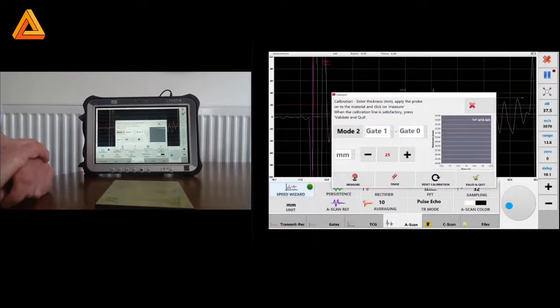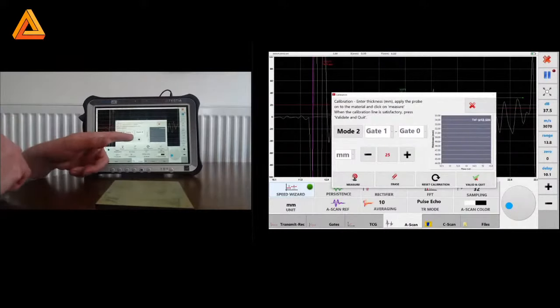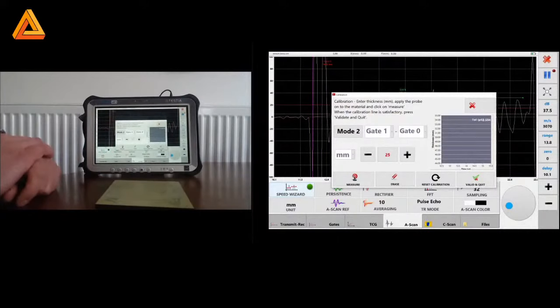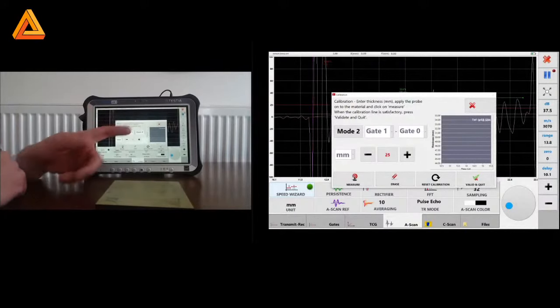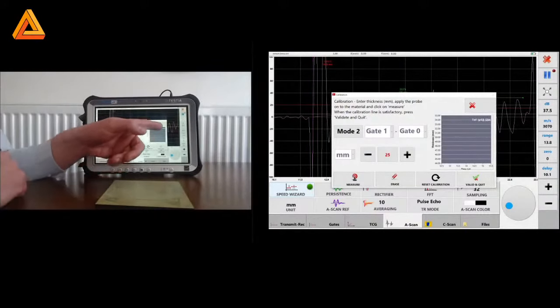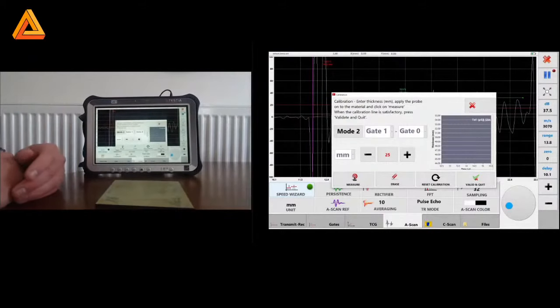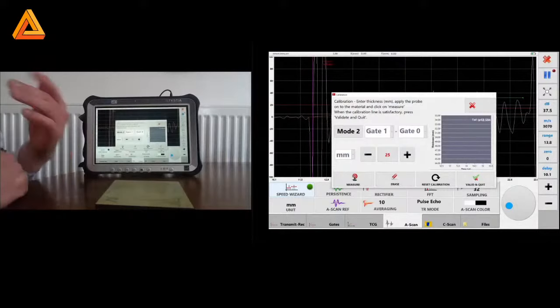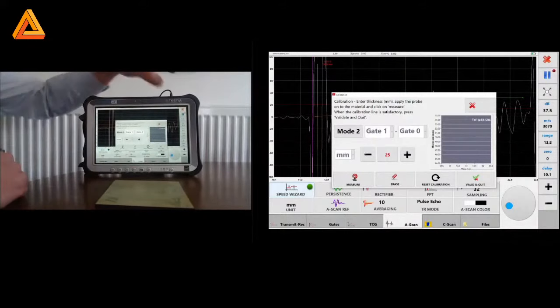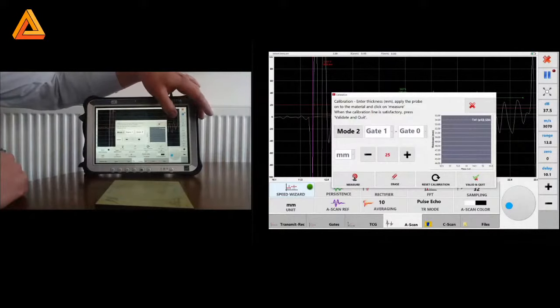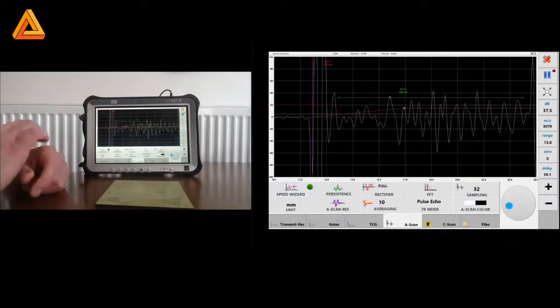Do an auto calibration for velocity, and we simply do this by entering in the thickness of the material where the red 25 is, and we can do this for multiple steps, and the system will then produce a straight line graph. It's a nice visual representation, so if one of your calibration points is off, we can see it visually during calibration, and we can erase those points and start again. Once we're happy with it, we press validate and quit, and it will automatically calculate our calibrated velocity.